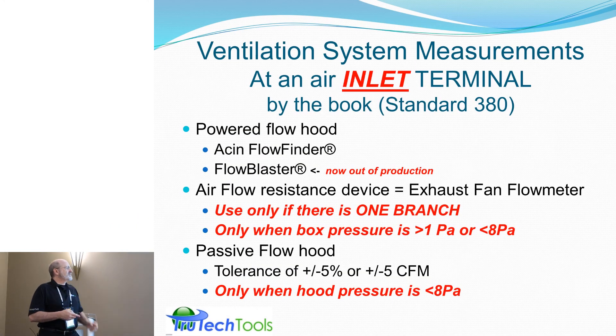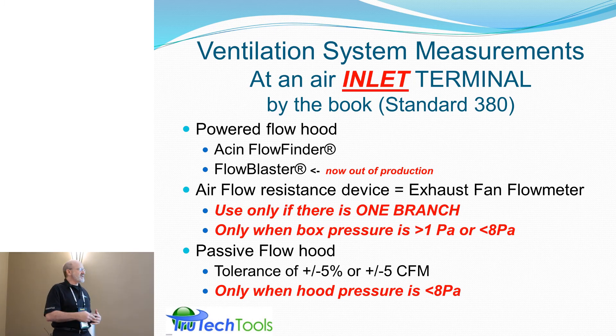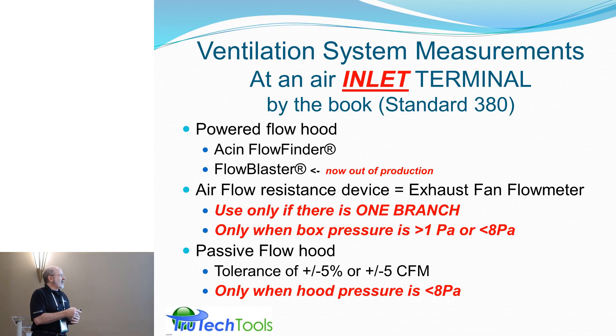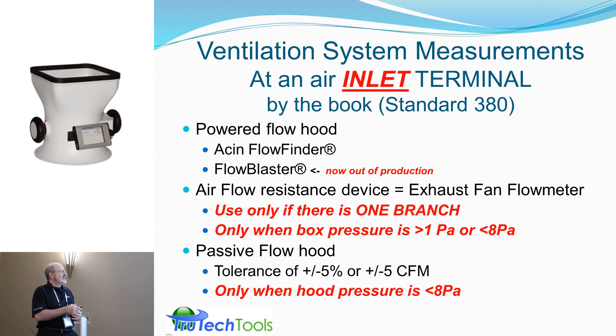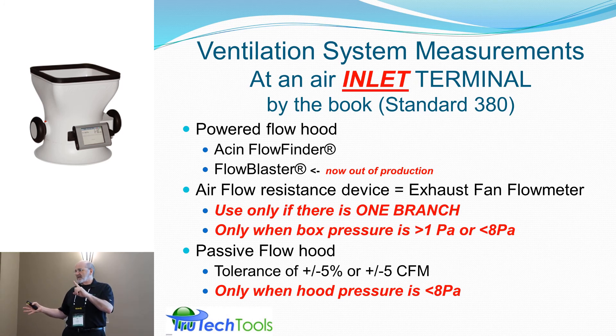At the air inlet terminal — and this is by the book in that standard where it talks about airflow measurement techniques — they recommend a powered flow hood. Right now it boils down to just one flow hood available that's a powered flow hood, because it is a superior measurement. This is also trying to explain the impact of different costs for test and measurement equipment, because they either do more for you or provide a better answer.